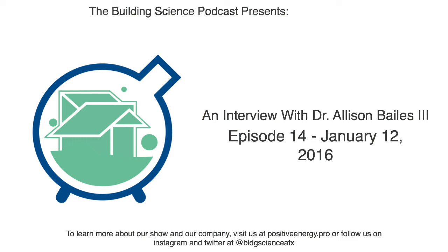Filtered air coming in from the outside. Yep. So if you run half an hour out of each hour instead of continuously, then you'd have to double that rate to 110 CFM. And if you do 15 minutes out of every hour, you quadruple that rate. Yep. So you have to bump up the rate if you decrease the amount of time that you run, if you run intermittently. Right. Yeah.